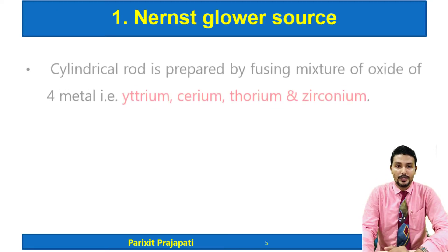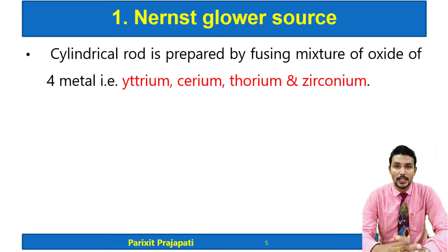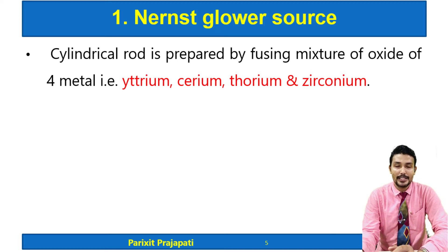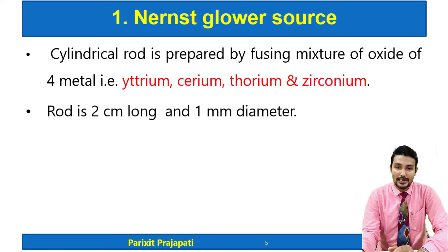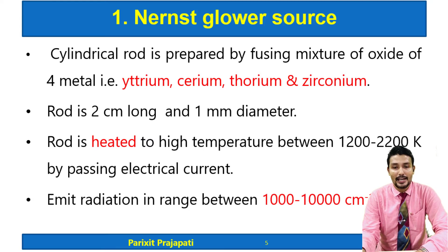The Nernst Glower source contains a cylindrical rod prepared by fusing a mixture of oxides of four metals: yttrium, cerium, thorium, and zirconium. The oxides of all four metals are made into a cylindrical rod of 2 centimeter length and 1 mm diameter. The rod is heated at high temperature between 1200 to 2200 Kelvin by passing electrical current, and it emits IR radiation between 1000 to 10,000 reciprocal centimeters.